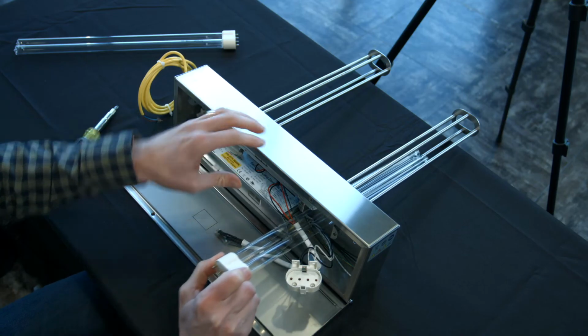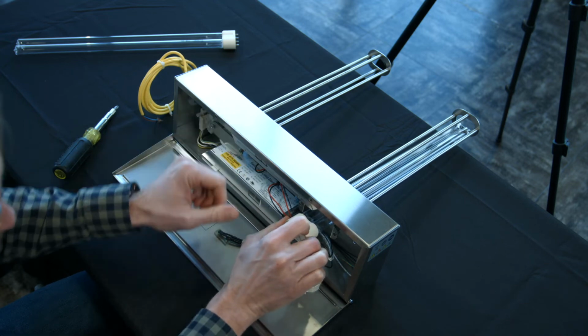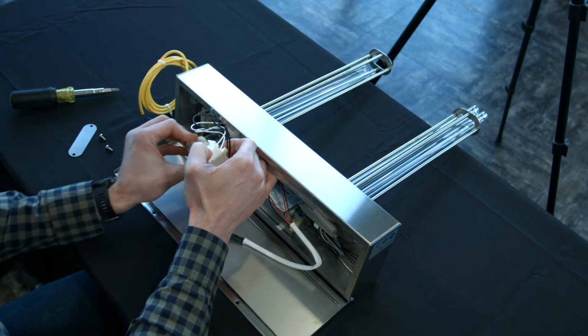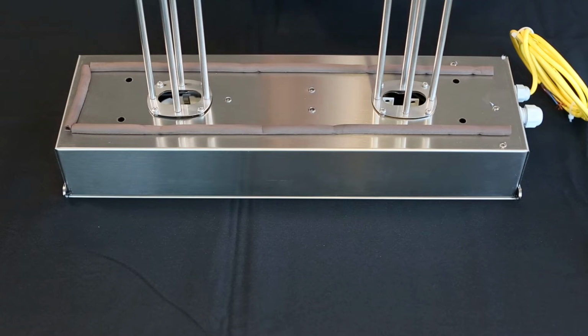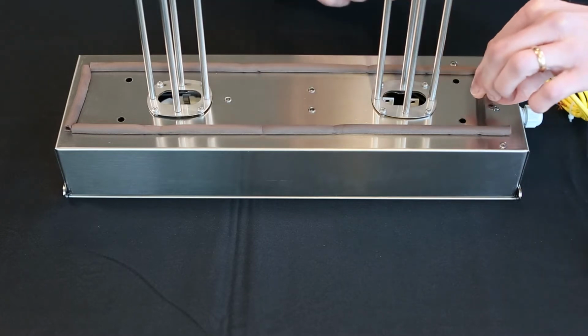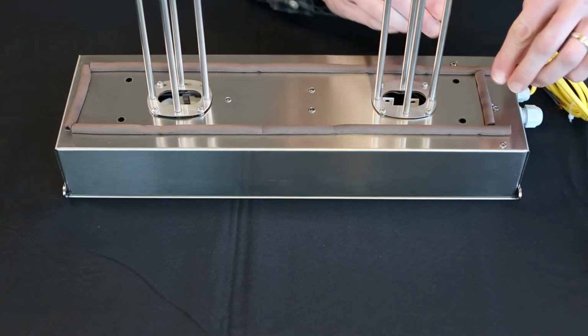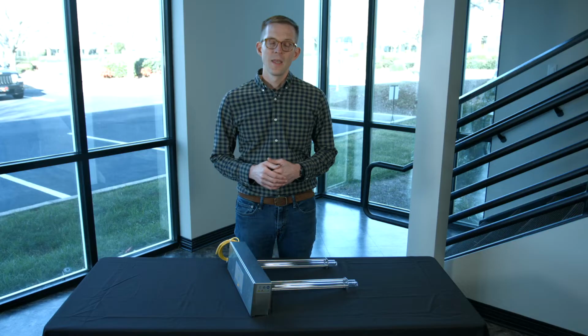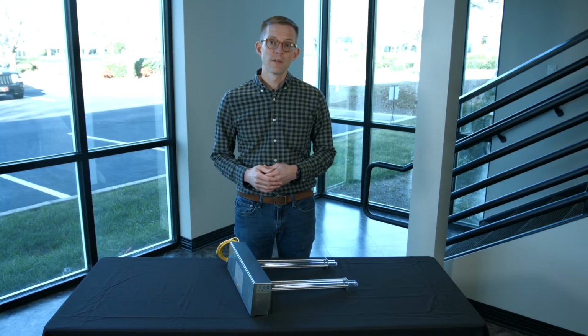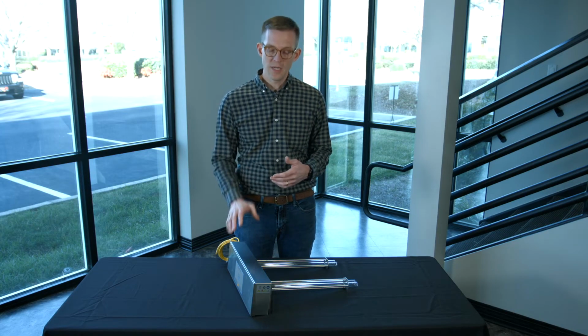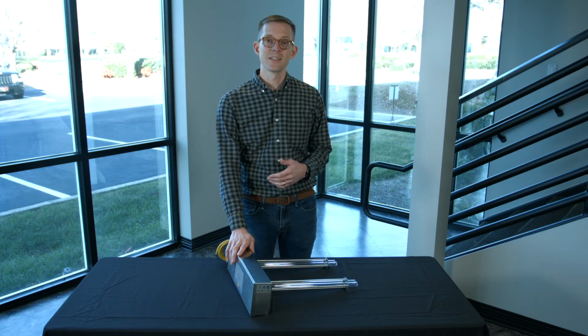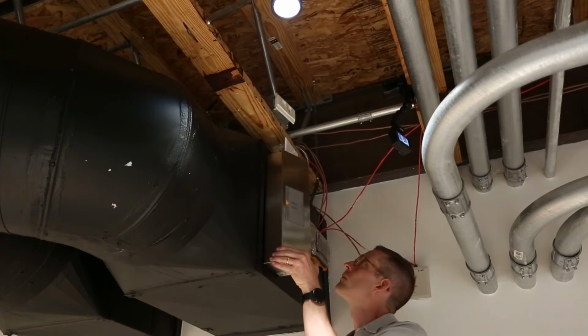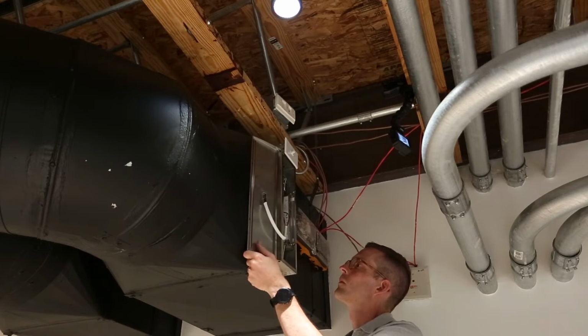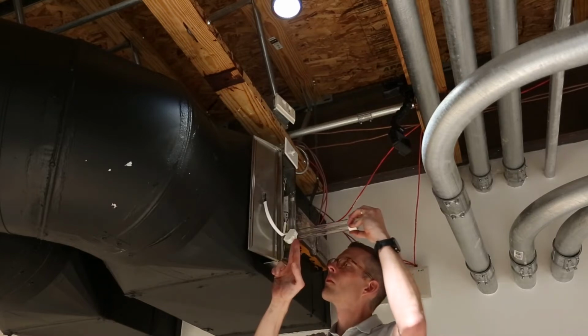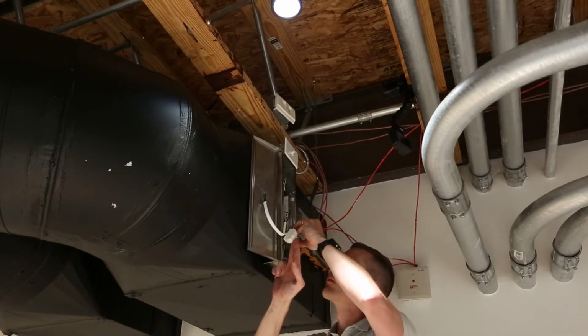The UV duct fixture incorporates 2 UVC lamps that stick into the ductwork, and there's a gasket that seals this against the outside of the ductwork to make sure that the install is nice and tight. Any maintenance for the UV duct fixture is also very easy because this box is accessible from the outside of the ductwork. We can open up the unit and replace any lamps from outside of the ductwork as necessary.